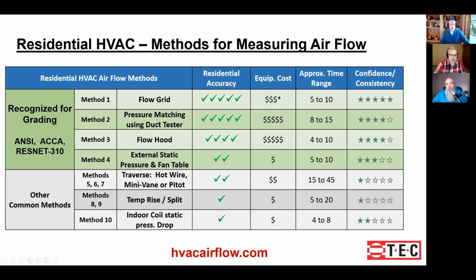The pressure matching method with the duct blaster is really sort of a gold standard way to do it, but it's expensive. If you don't already have a duct blaster for measuring duct tightness, that's a lot of money to be just measuring airflow. But it continues to be the gold standard. It takes a little longer, and it requires a little more expertise to make sure you've got it set up correctly. The flow hoods can be a very good way to do it.